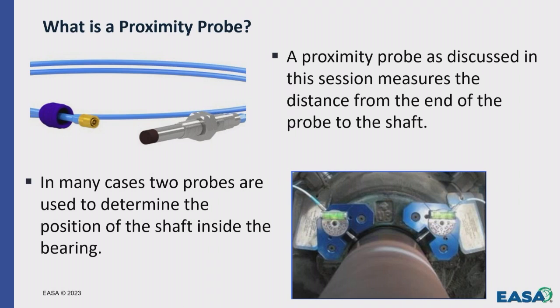So, when we talk about a proximity probe in this instance, it's just simply measuring space, measuring the gap. They have a lot of other applications in industry, but this is what we're going to talk about today. In most of the cases for electric motors, they're going to feature two probes, and we can calculate the exact position of the shaft inside the bearing by measuring that distance in the movement. In some cases, you'll find where a customer is using a single probe for monitoring and trending, and that's fine. I would compare it to using a single accelerometer in one direction as opposed to taking all three directions when you do traditional vibration analysis. Better than nothing, but using two at once is preferable.